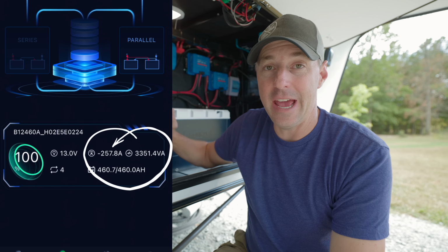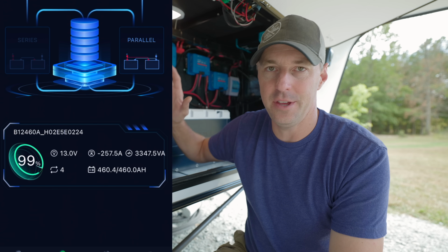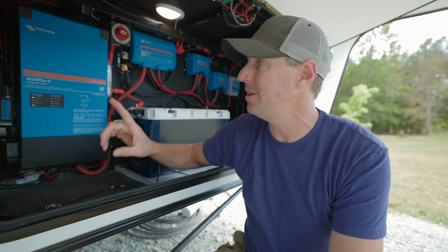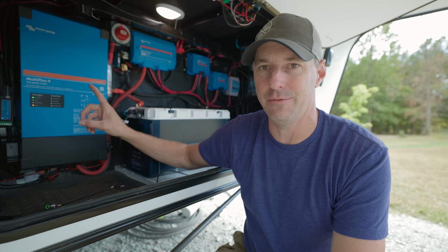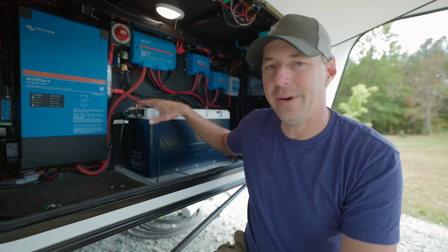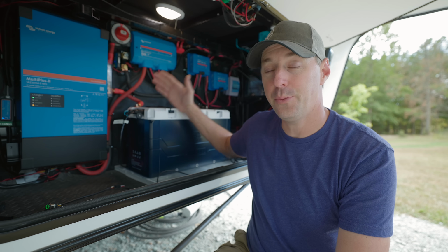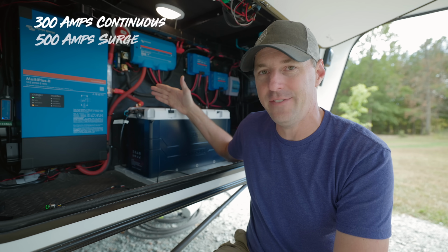This test turned out exactly as I expected. The battery had no problem keeping up with the demand of the inverter, and the problem was the inverter was maxed out. But the point is the battery had no problem because it has 300 amps out continuous, with a 500 amp surge.